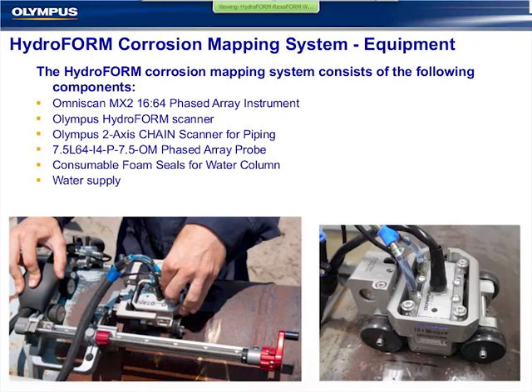So the system consists of the OmniScan instrument, a minimum of a 16:64, since the typical probes are 60 or 64 elements and are not used with a second or third probe. That instrument is sufficient for the overwhelming majority of these customers. Any of the existing 32:128s, 16:128s, of course, are compatible as well.